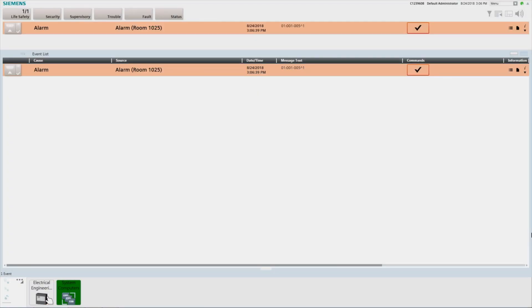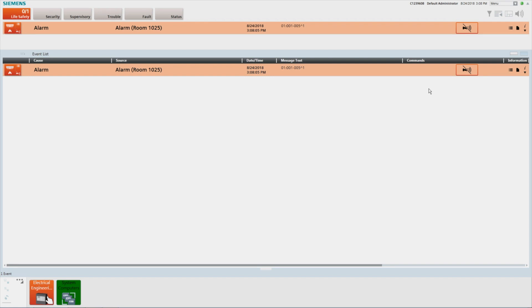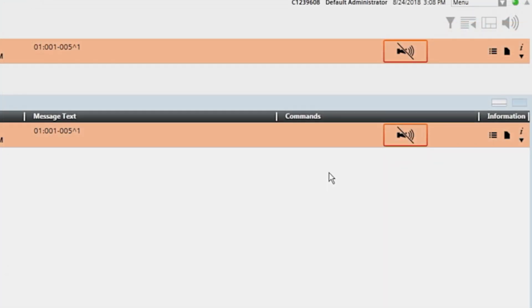I'll now demonstrate the usage of the system. An alarm is indicated in the summary bar by the red flashing life safety lamp and the red flashing fire panel icon in the node map. In addition, a red event will be displayed in the event list with the red flashing event icon and the workstation audio indicator will sound. To acknowledge the alarm, press the acknowledge button located in the commands column in the event list. The workstation audio indicator will be silenced, and the life safety event lamp, event icon in the event list, and the source fire panel icon in the node map will change from flashing to steady. As you acknowledge an event, the next available command in the commands column changes from acknowledge to the silence audibles command button.